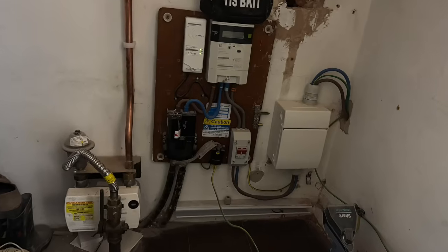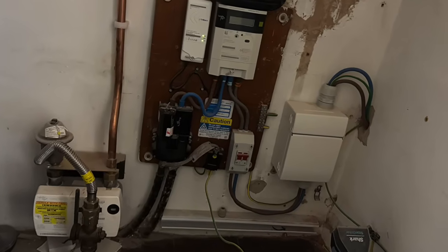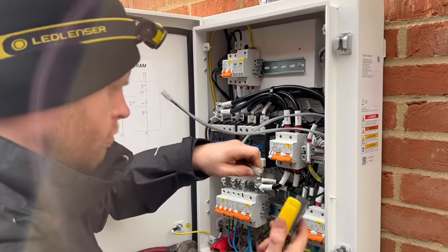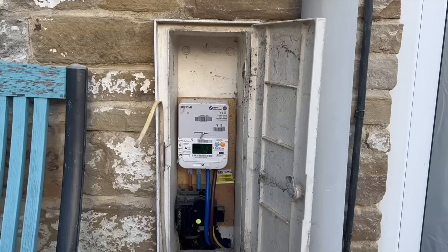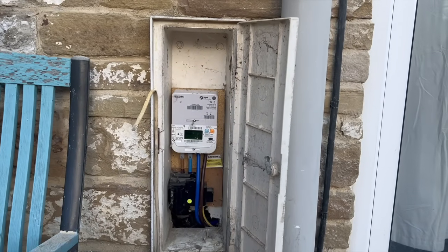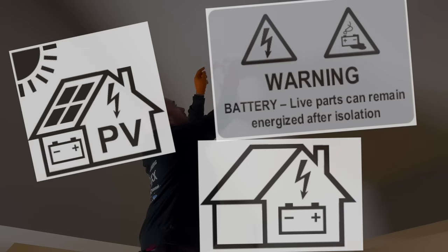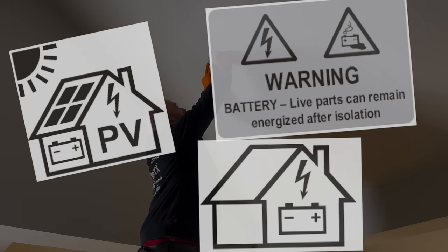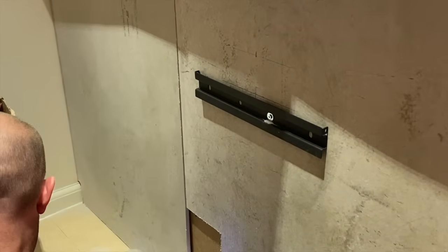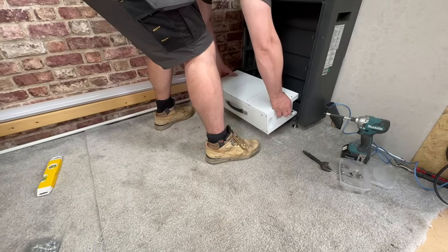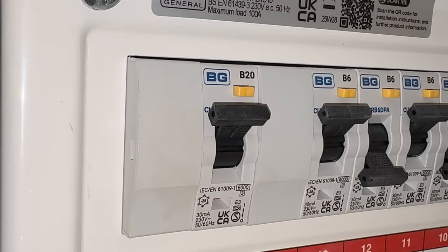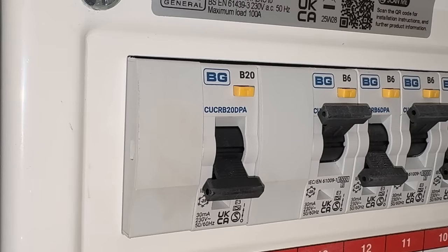And you may need to install warning notices in different locations depending on the installation. A warning notice must be fixed at the origin of the installation, at each consumer unit or distribution board supplied by the battery, and importantly, at the metering position if that is remote from the consumer unit. So anyone working on the installation is aware that there is another source of supply. So this is not just about adding a battery to an installation, it changes how the system behaves, how it's protected, and how it needs to be approached when you are working on it.